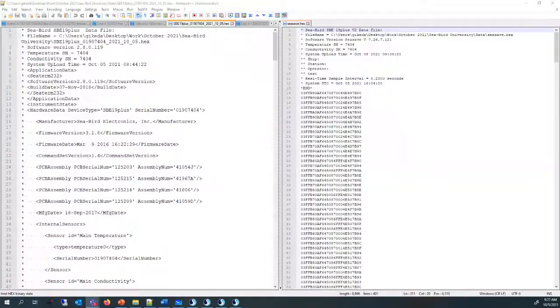Okay, the next one is: is the data received in real time the same as data stored on the SBE 19plus V2 internal memory? So yes, though a lot of it depends on what the actual transmit rate of the sensor is. If you're using a serial cable that's really long, your baud rate's going to be a lot slower, so you can't actually use the full 4 hertz. You're going to have to average, and then send it to real time. The instrument will store the exact same hex file as that averaged data that it's sending to the computer. If you're able to use a deck box, it has really fast transmission rates, and you're able to get the full 4 hertz sampling, both on your computer attached to the deck box and on the instrument itself.